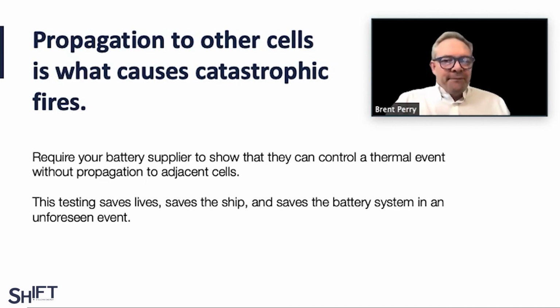Now, propagation, that is the problem. How do you manage propagation? The good thing is the current testing regime introduced by UL last year really does force all of us as battery designers and engineers to deliver a system that can pass this without propagation. By introducing a thermal runaway at the cell level and determining whether or not you have propagation, you really are creating the best possible test, one that reproduces the worst thing that can happen in the field. From here, true safety, true design, and true standards can really evolve.